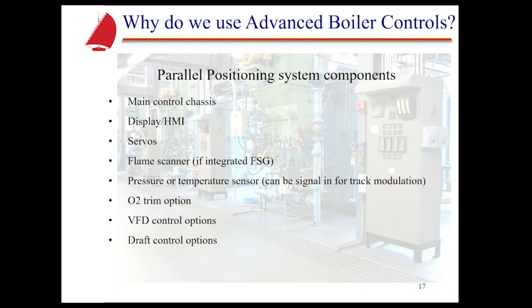A pressure or temperature sensor. You're going to need that if you're going to be using, for instance, the internal load control to control around a steam pressure, or if it's a hot water application, a temperature sensor. Or you may end up using both if you're going to go into a hot water standby, and some will allow you to do that. Now, some of these systems will not even use a sensor input. They will just be set up for track modulation. What I mean by that is some type of external control will control the modulation by, like, a 4 to 20 milliamp signal going back to this particular parallel positioning system.